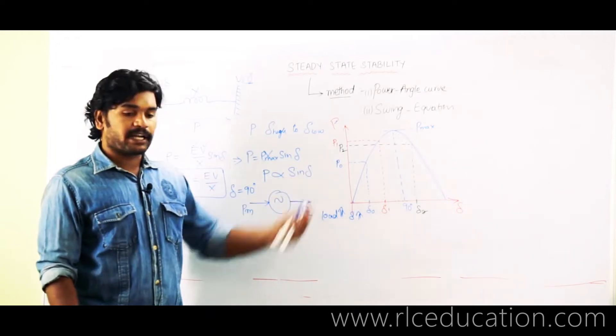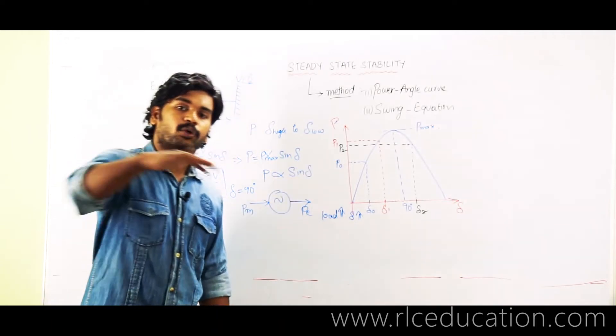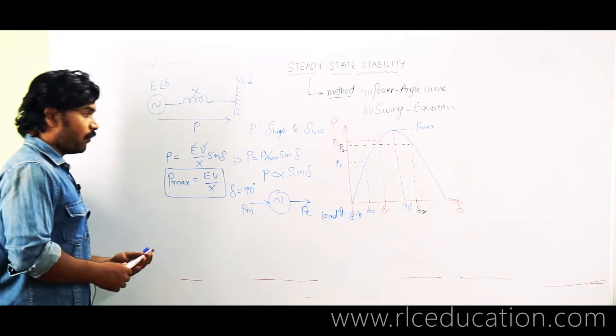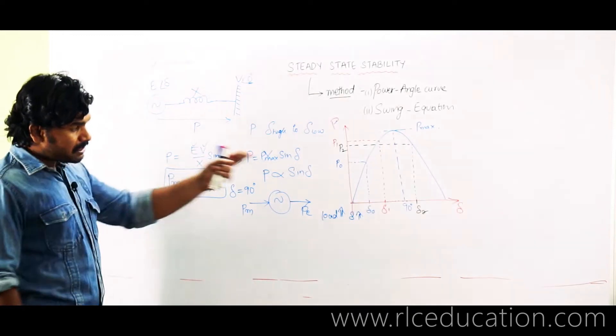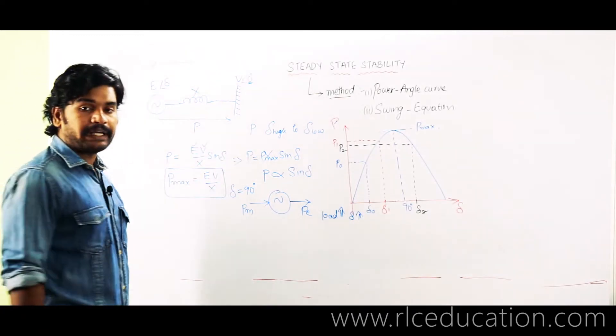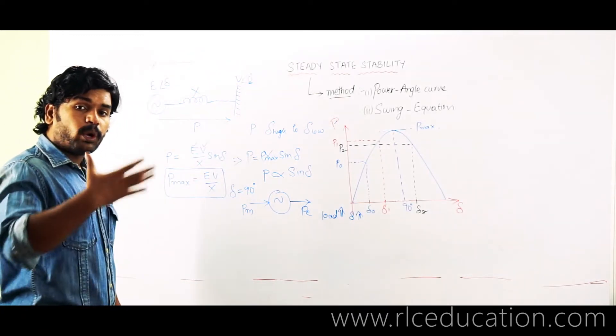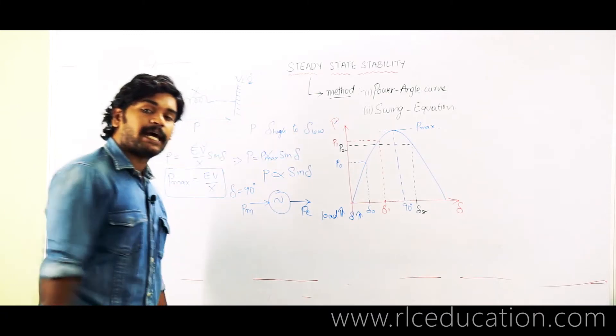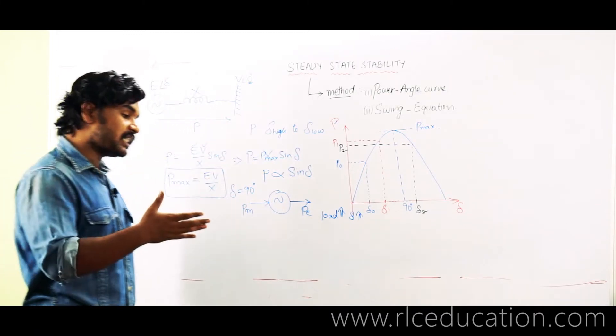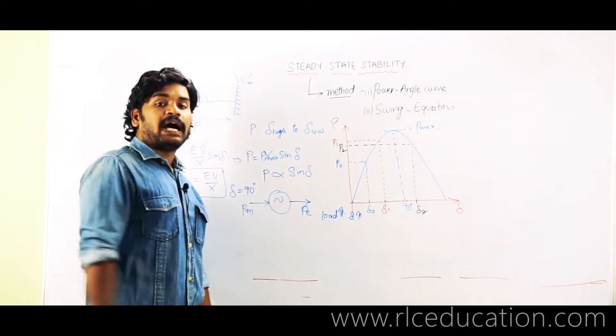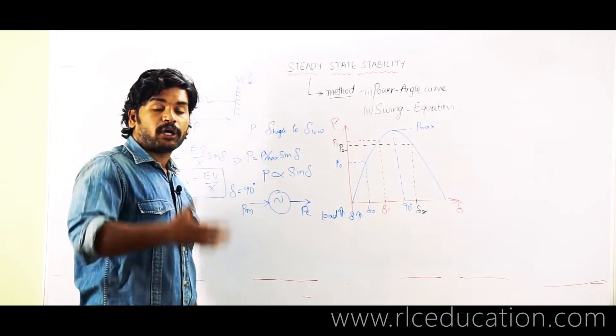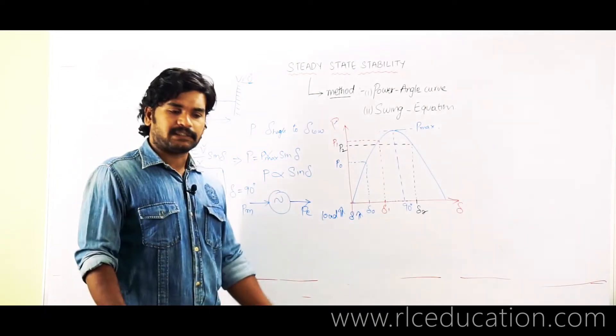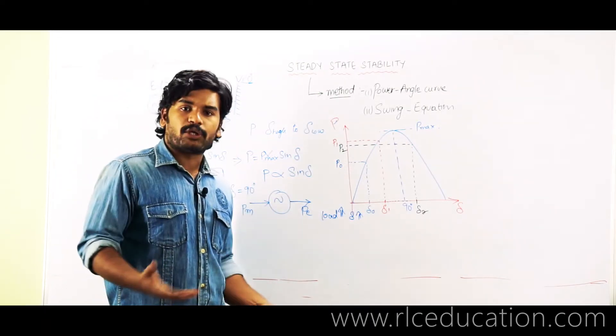That means the generator has entered into the unstable zone of operation. Therefore, from this particular power angle curve, I can say what is the maximum amount of load that I can apply on a particular generator before it is driven into an unstable state, or what I can call loss of synchronism.